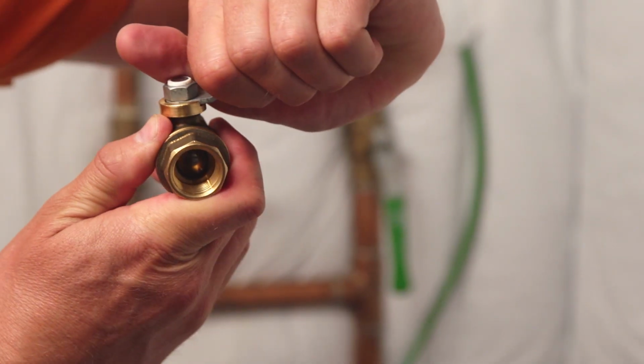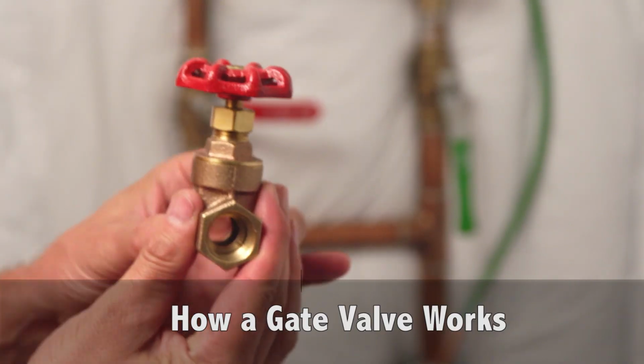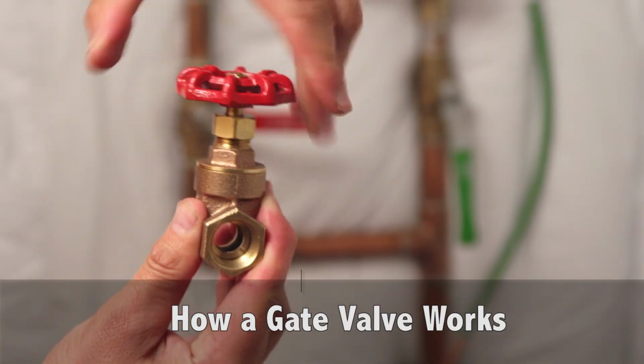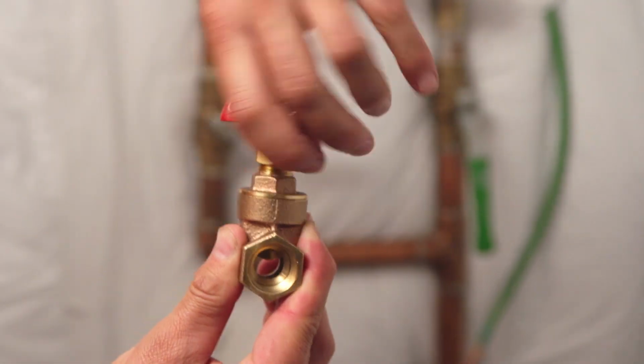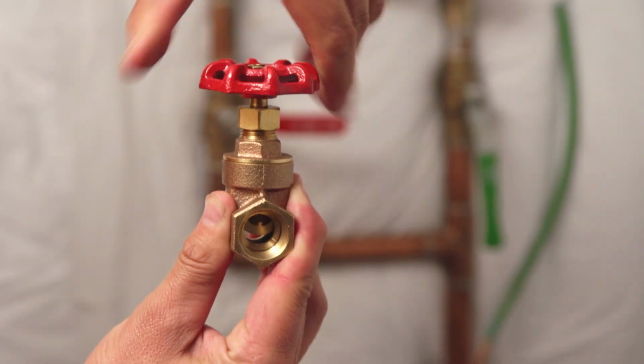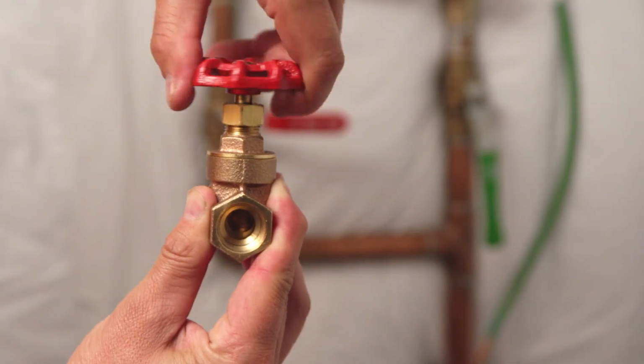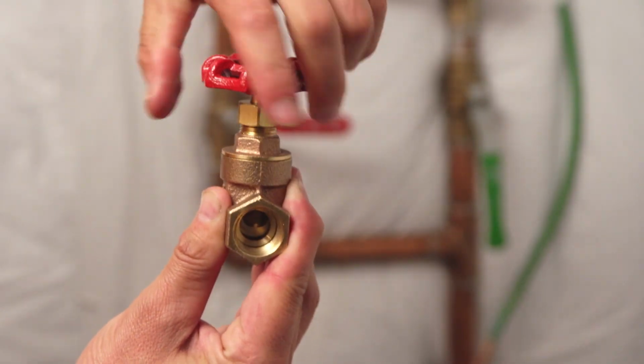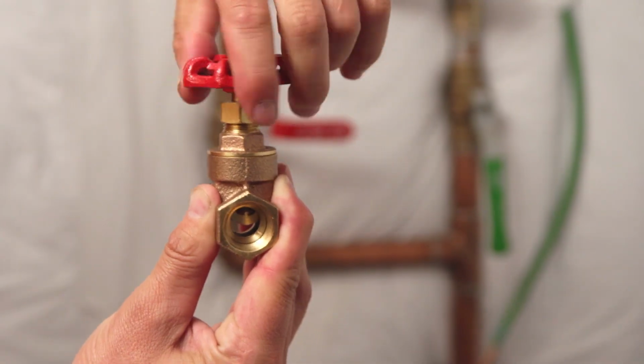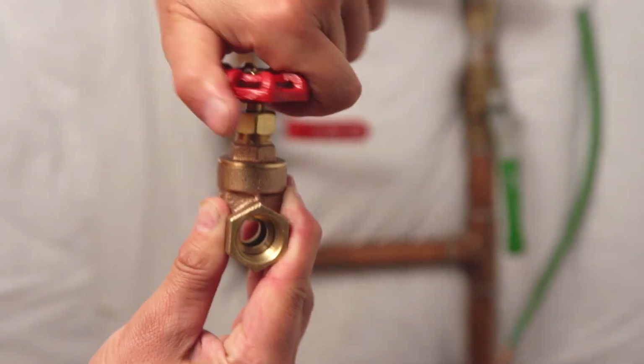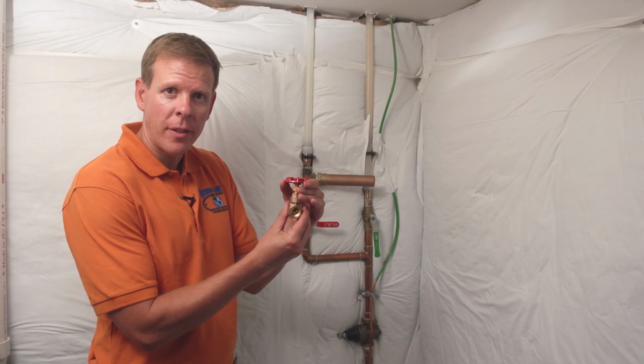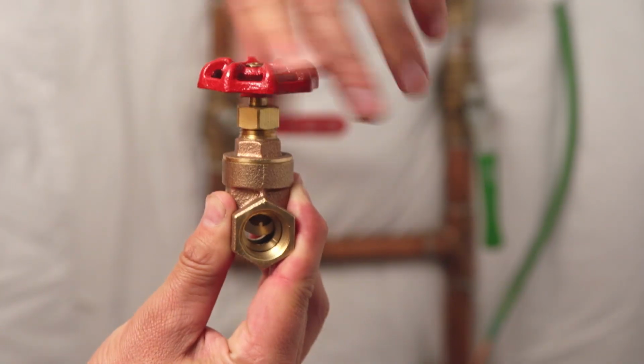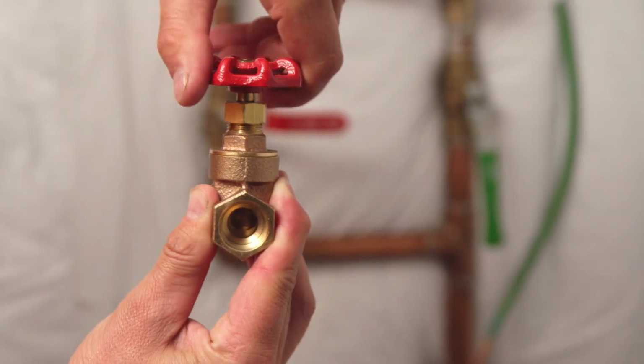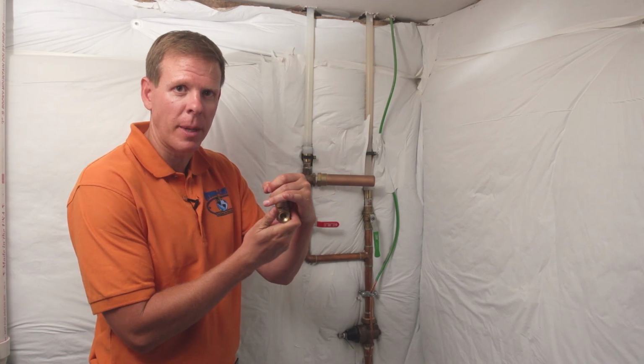and you can see there's a ball inside of it that opens and closes. And here is the inner workings of a gate valve. As you can see, as I turn the valve clockwise, the gate comes down and closes. And as I turn it counterclockwise, the gate comes up and opens. It is very important, especially as these get older, they might get some hard water deposits on the valve itself.